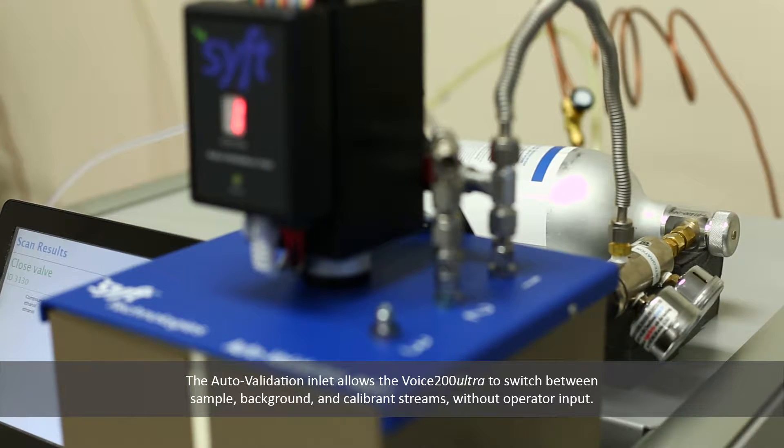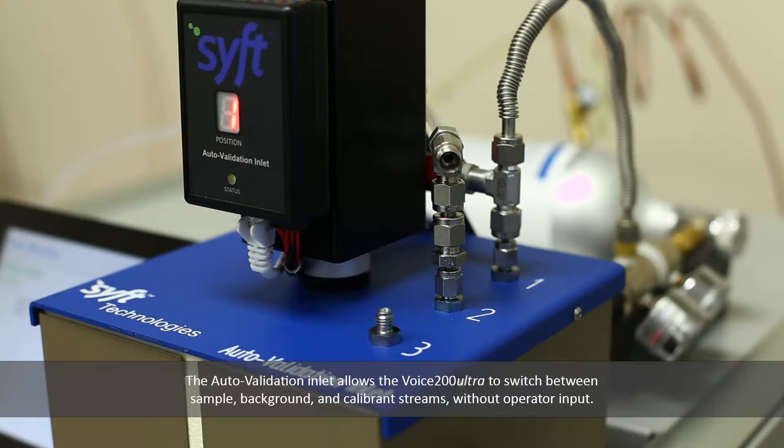Introducing Syft's new Auto Validation Inlet, which allows truly automated 24-7 operation of the Voice 200 Ultra. The Auto Validation Inlet allows the Voice 200 Ultra to switch between sample, background, and calibrant streams without operator input.